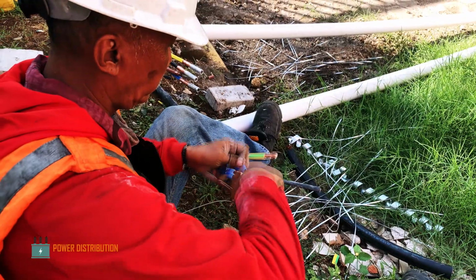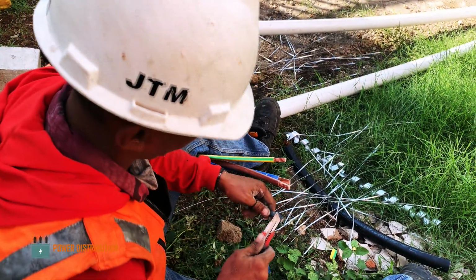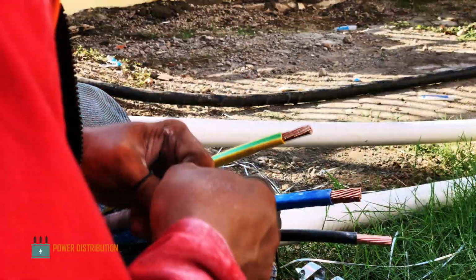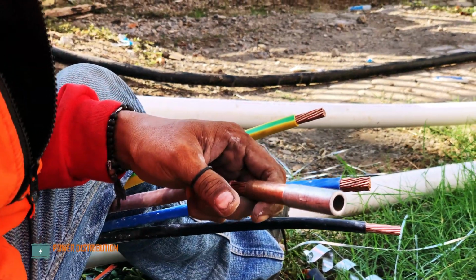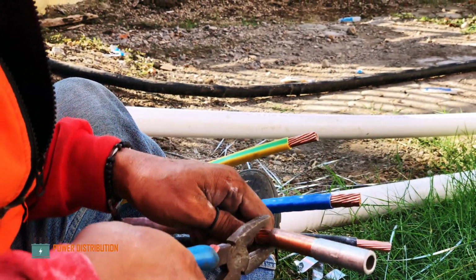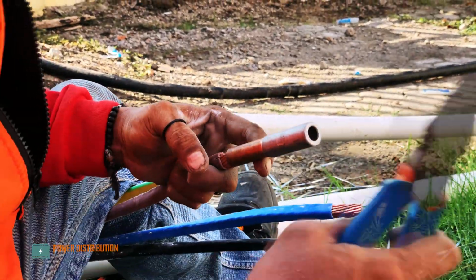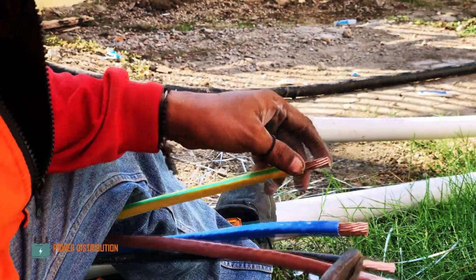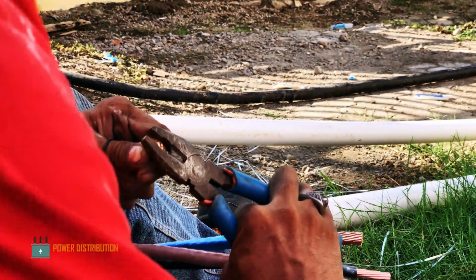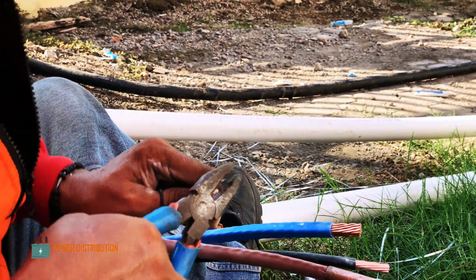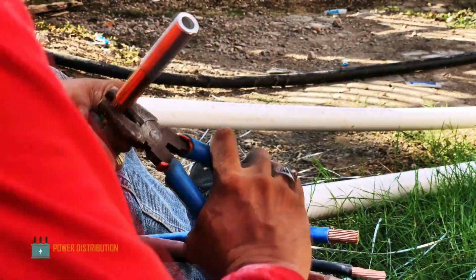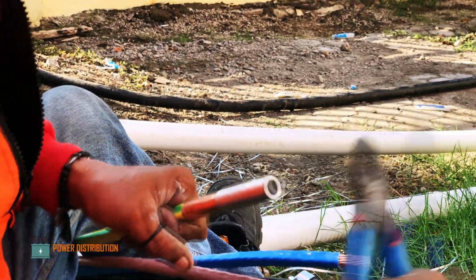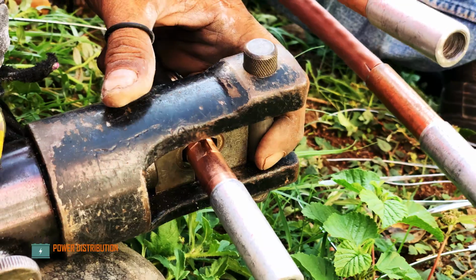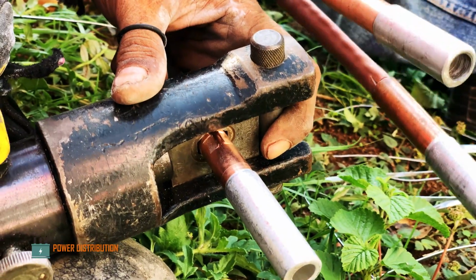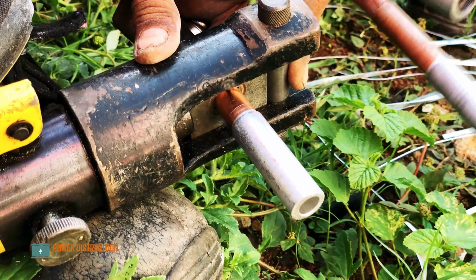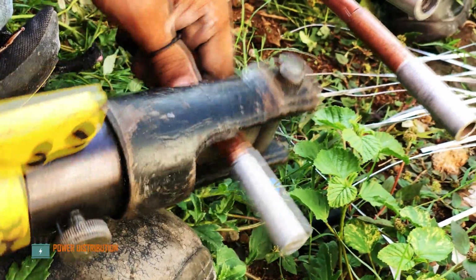Then the crew peeled the tips of the cables in order to expose some of the bare copper in order to install the copper to aluminium connector. This kind of connector is commonly called compressed connector because we use hydraulic press to secure the connector with the conductor itself. We use aluminium to copper connector because the existing secondary surface wire is aluminium wire.